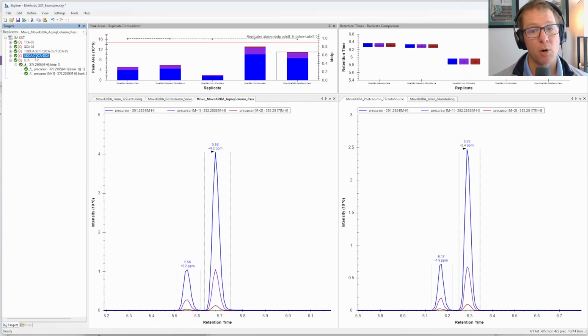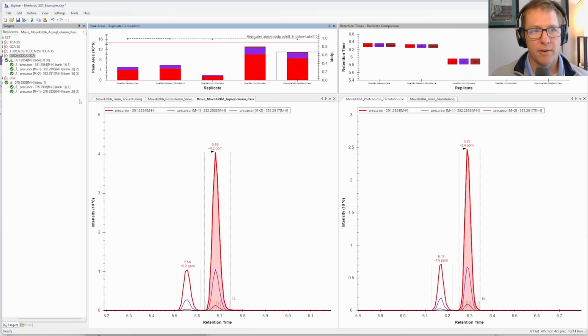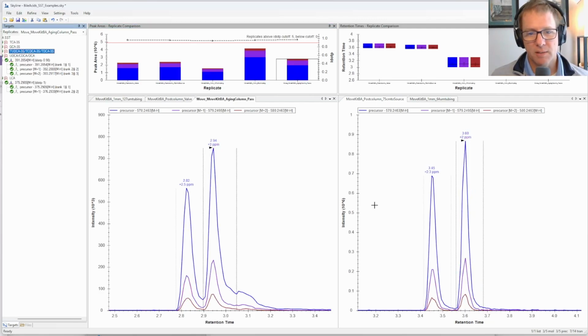If you have post-column broadening, nearly every peak will be affected in essentially the same way. That broadening mechanism is typically irrespective of molecule class. Whereas if you have something that's more related to the separation itself, some peaks may show broadening due to other effects in the separation that may be unrelated to the post-column configuration.